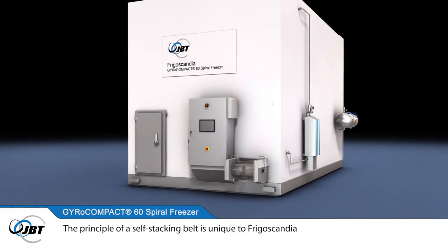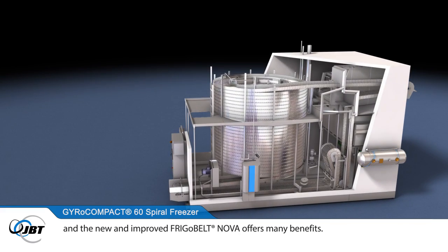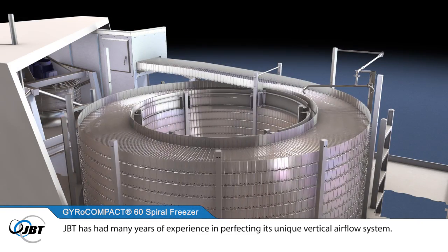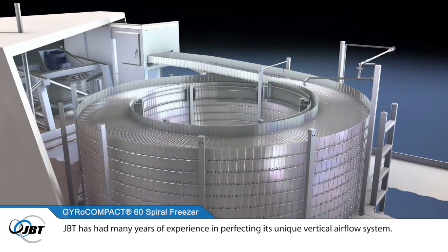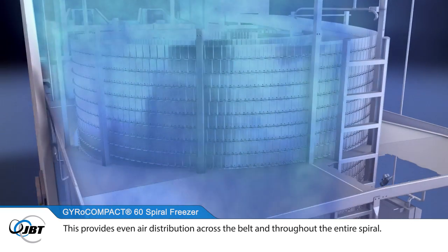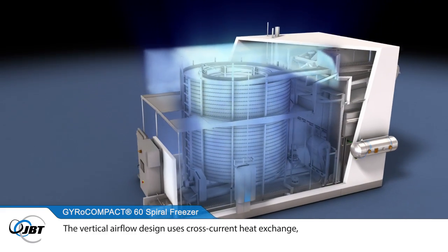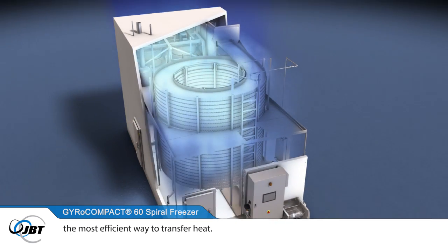The principle of a self-stacking belt is unique to Frigoscandia, and the new and improved Frigobelt Nova offers many benefits. JBT has had many years of experience in perfecting its unique vertical airflow system. This provides even air distribution across the belt and throughout the entire spiral.